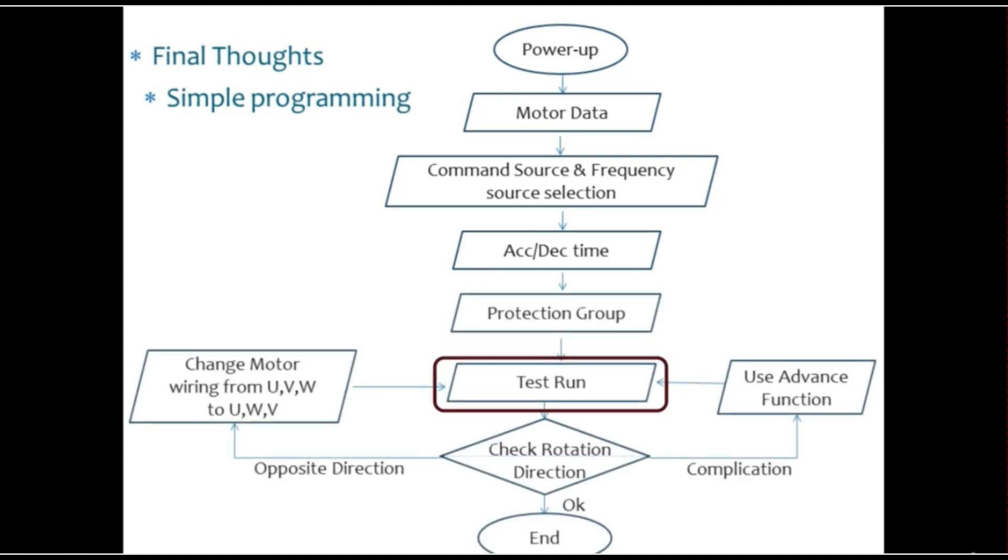In test run, check the motor's direction. If the direction is opposite, change the order of motor connection. That will be from UVW to UWV.